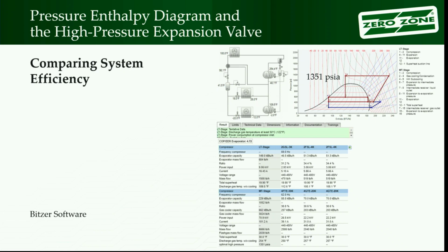So anyhow, it gives you the capacity of the system, and what you want to really look at, we're going to watch how it moves on the next slides, is this vertical position. What do you guys think about how much gas do you think we have versus liquid there? 65. Yeah, 65, 35. We got more liquid, right? We're definitely past the 50% mark, so we're over there on the liquid, and we're letting the software, everybody knows, it's not a secret, calculate the best position. So our controller will be trying to maintain 1351 PSI as well.